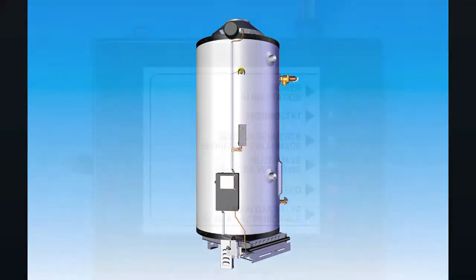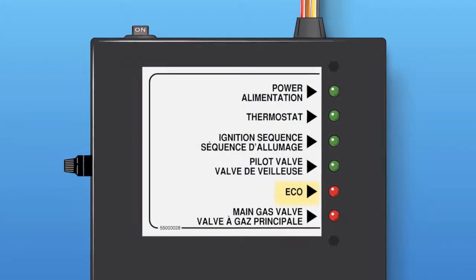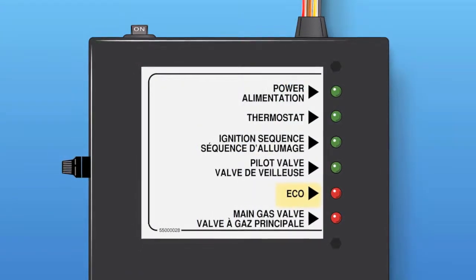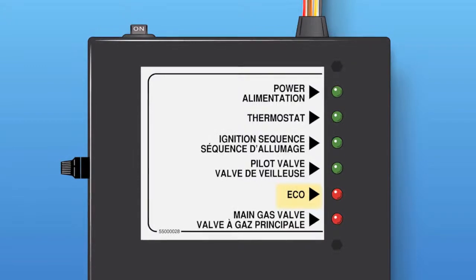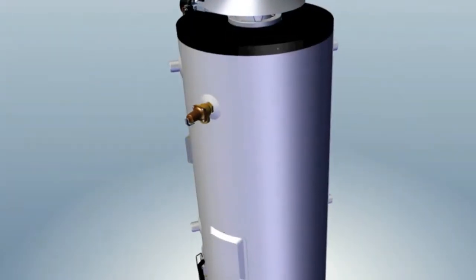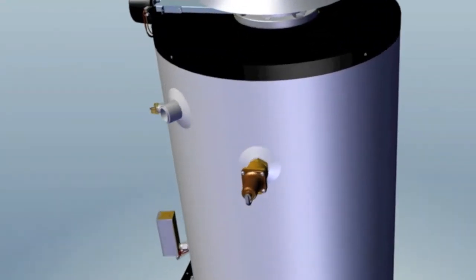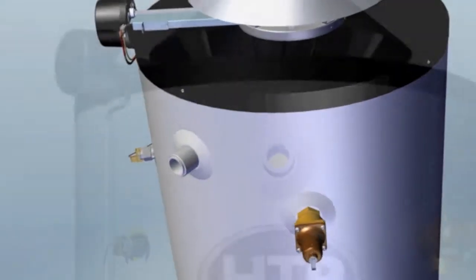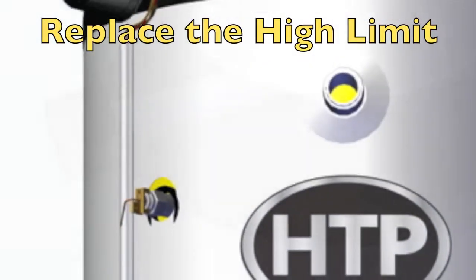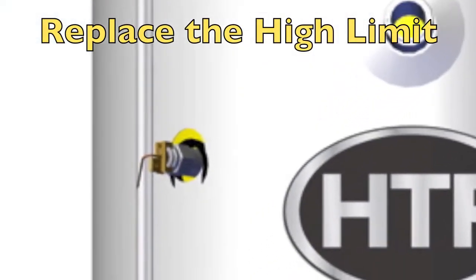Step 5: ECO. If the ECO LED is red, then the ECO is open and you must allow the water in the tank to cool and the ECO to reset. If the ECO continues to trip, then the thermostat high limit control is defective. Replace the high limit.